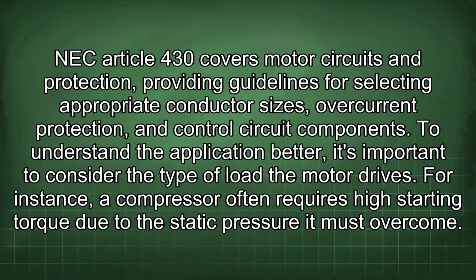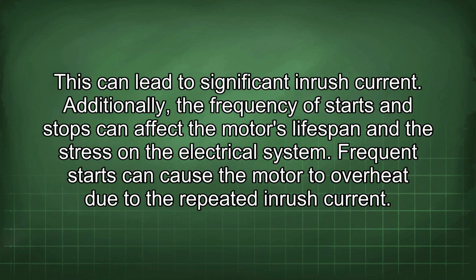To understand the application better, it's important to consider the type of load the motor drives. For instance, a compressor often requires high starting torque due to the static pressure it must overcome. This can lead to significant inrush current. Additionally, the frequency of starts and stops can affect the motor's lifespan and the stress on the electrical system. Frequent starts can cause the motor to overheat due to the repeated inrush current.